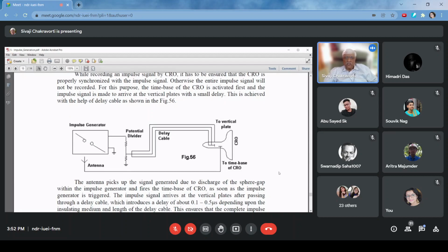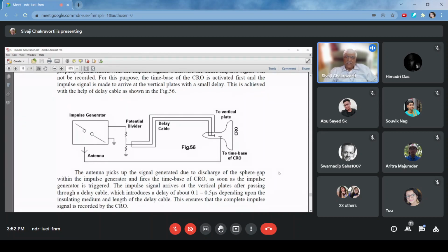We have to ensure the signal comes to the y-axis after the sweep signal has started. How do we do it? Typically, we measure this high voltage using a potential divider, because a 400 kV impulse cannot be fed to any electronic circuit. So we use a potential divider to reduce the voltage, and that reduced voltage comes through a cable to the y-axis.